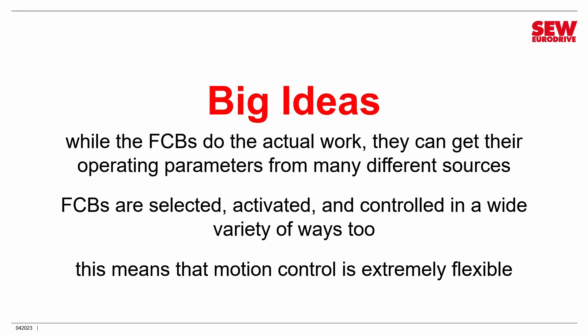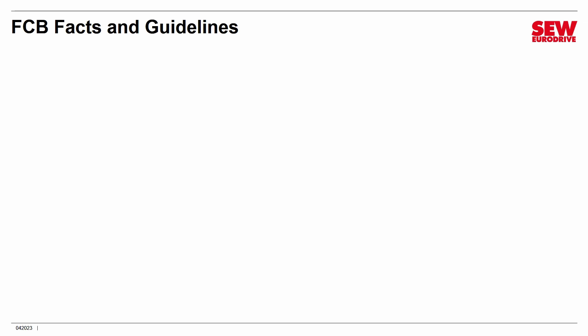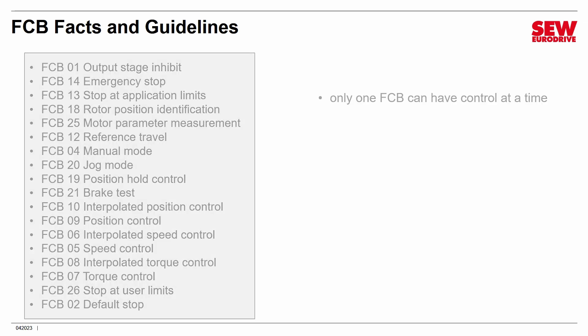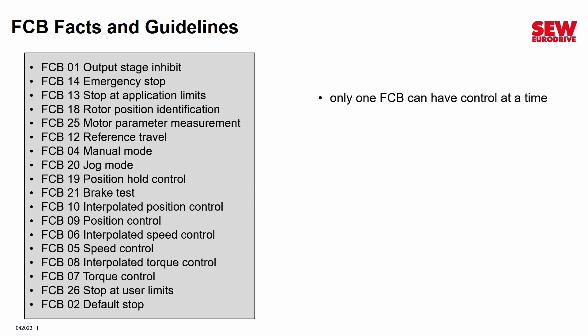FCBs can be selected, activated, and controlled in a variety of ways, and that means motion control is extremely flexible. FCBs can be selected, activated, and controlled by I/O, parameters, or the fieldbus — there are a lot of possibilities, and we're going to explore several of them throughout this class. One key fact: only one FCB can have control at a time. You clearly cannot have FCBs competing for control — that would be a dangerous situation — so from your list of FCBs, only one can be in control at a time.